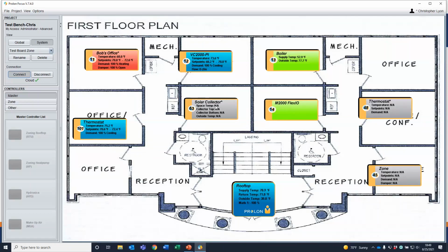Now, our registers for all of these Modbus RTU points are completely published. If it can be read from or written to, it is available to you, and we will hand those over to you. We're not going to assist in the integration, because if you're playing at that level, you should pretty much be able to play by yourself, but we will make all of our information available. It's not like some manufacturers where they say, oh yeah, you can talk to that chiller, but you can only talk to these four points when you need half a dozen or more. Everything in our controllers is available. You can bring Prolon into anything that can talk Modbus RTU, but you are not going to bring anything into Prolon. Prolon is only going to work with Prolon.